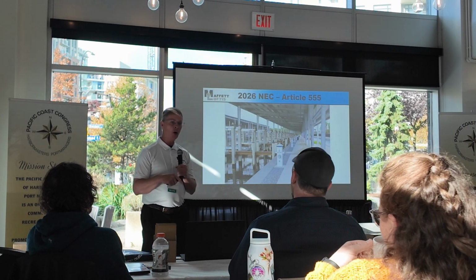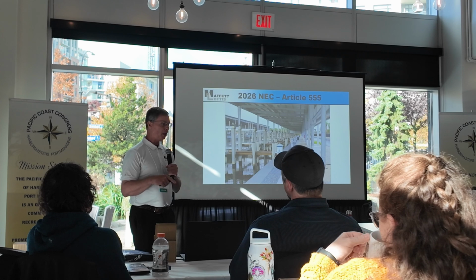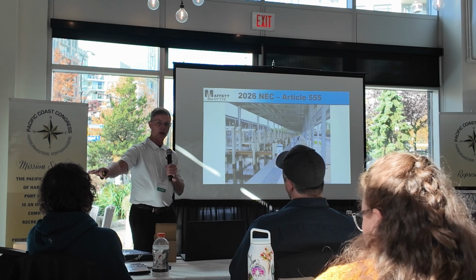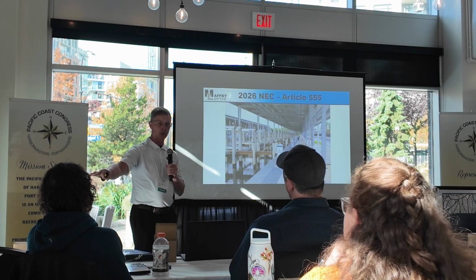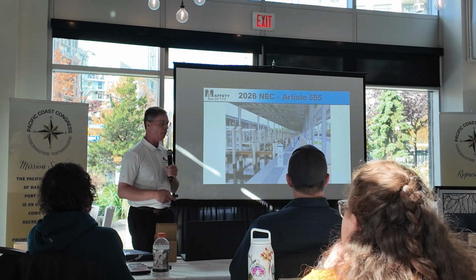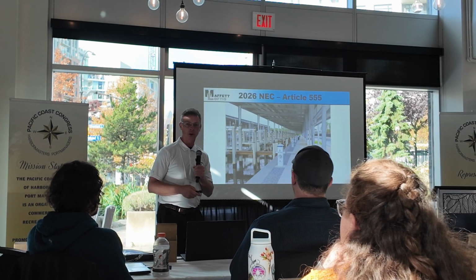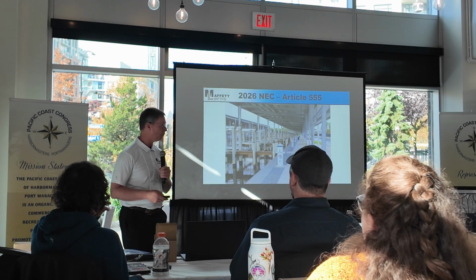So now in the 2026 code, it gives the AHJ permission to say, okay, I can ignore that, or the engineer to ignore those smaller loads and only do it for the big load. It helps out on the load service and the service sizes, so that will help the marine industry.